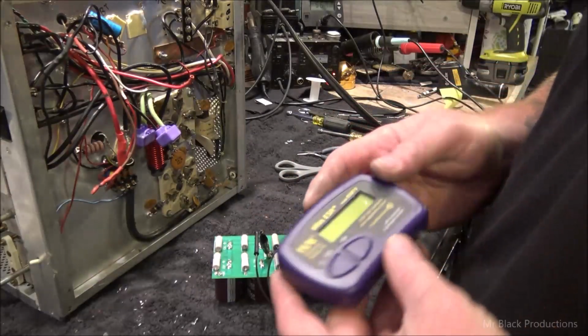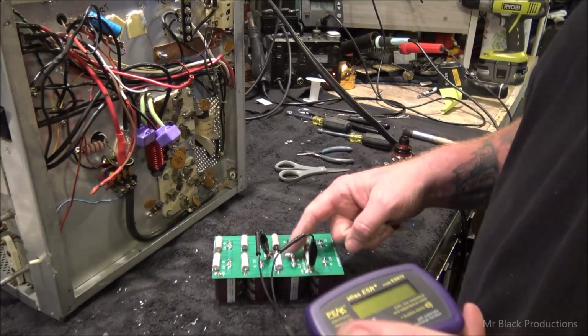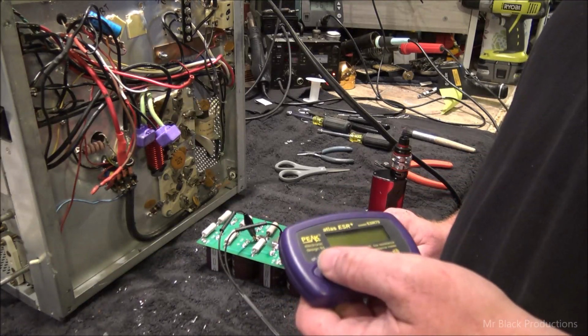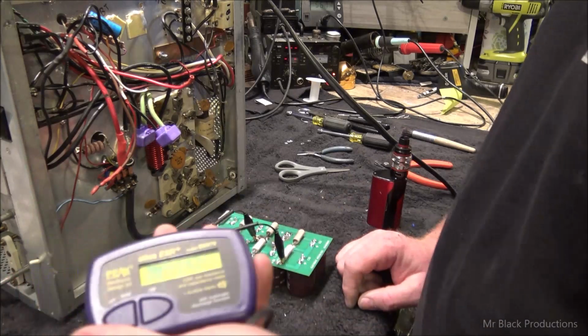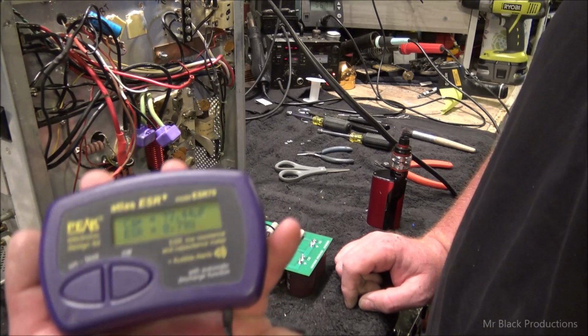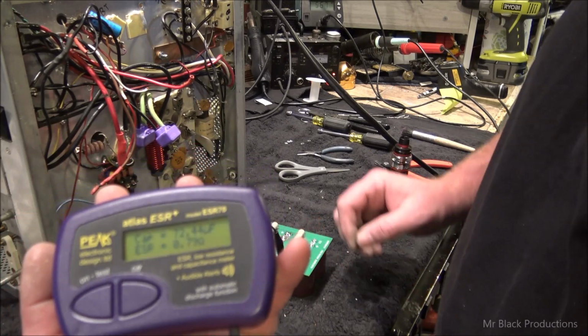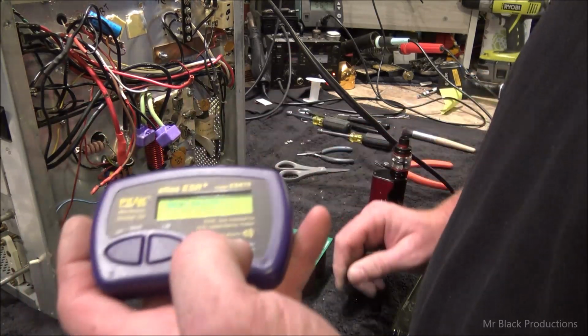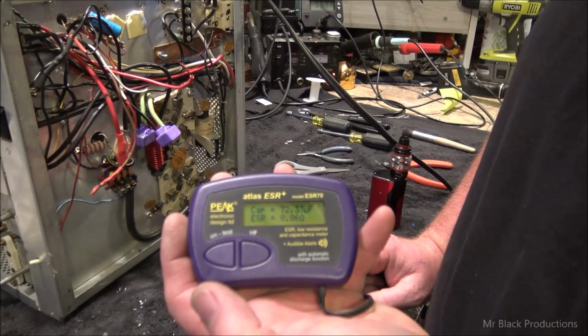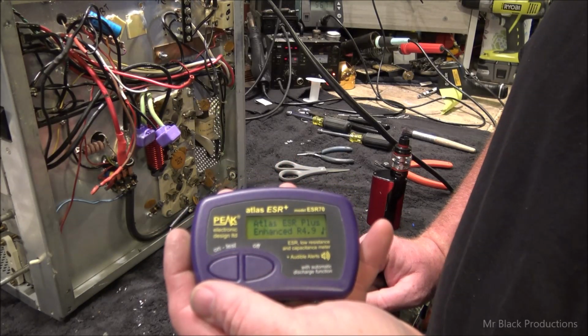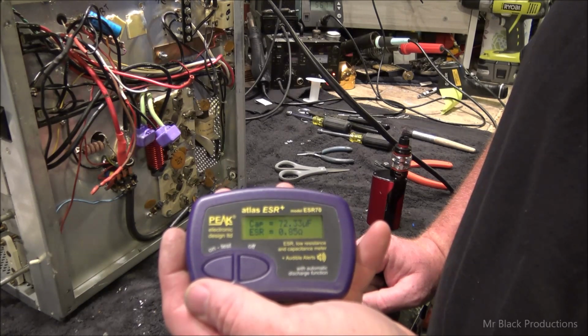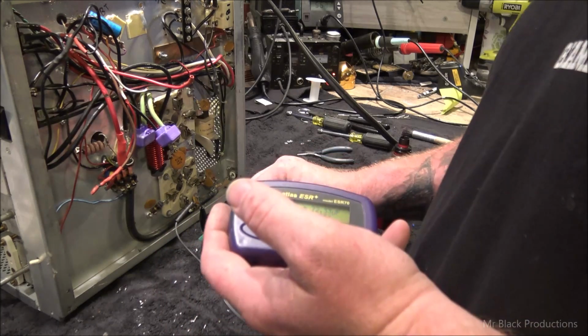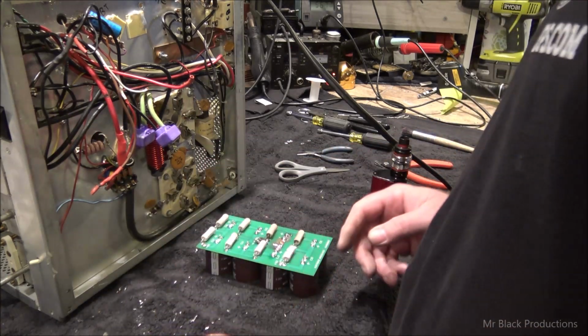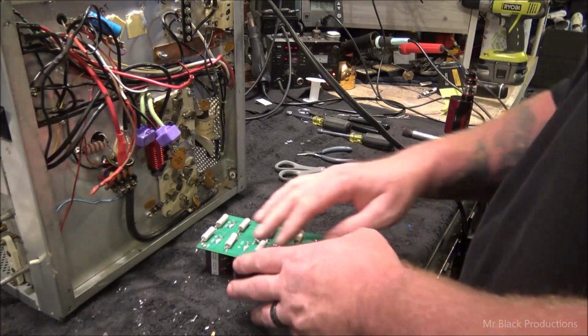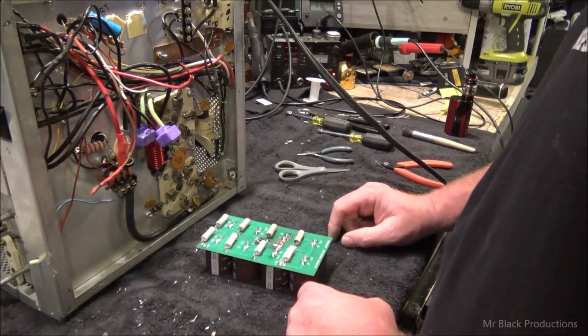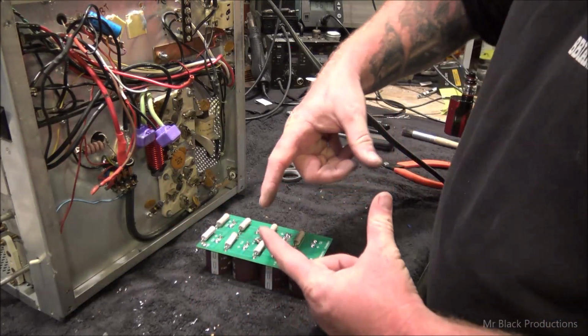Let's test one last thing. So now what we're going to test is our conductivity through all the caps in the chain for a total sum value of, should be about 72, 73 uF. Look at that. We should see this on the other side too. I'll live with that. Balanced. What that tells us is that we got conductivity through the entire circuit. Both sides.